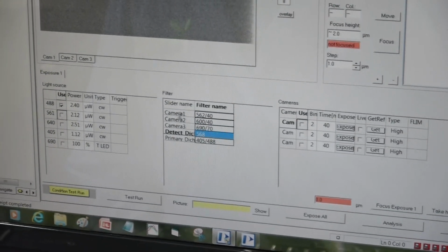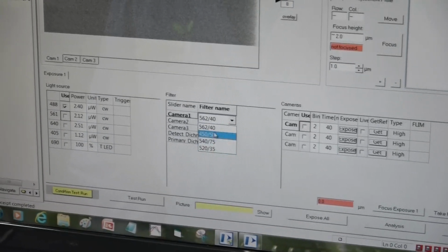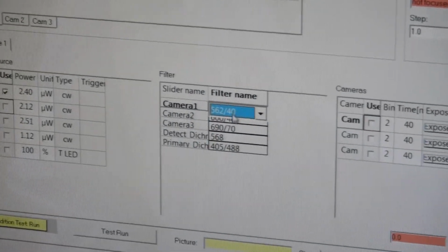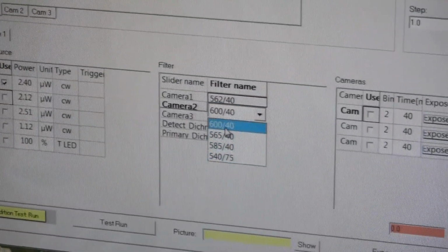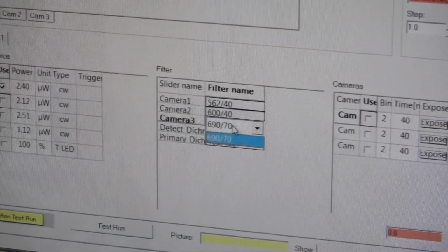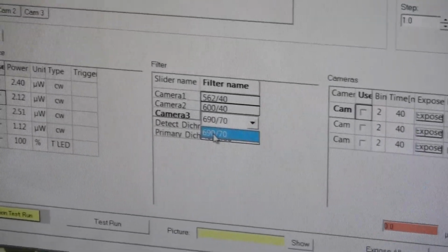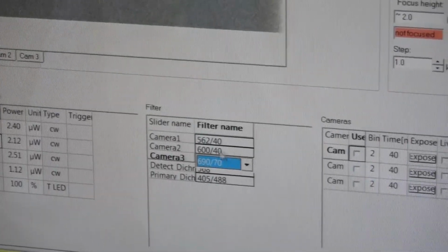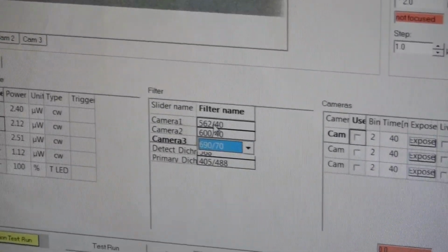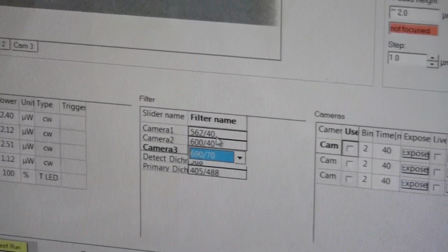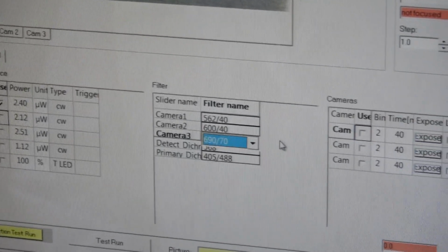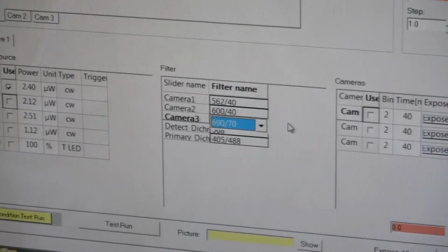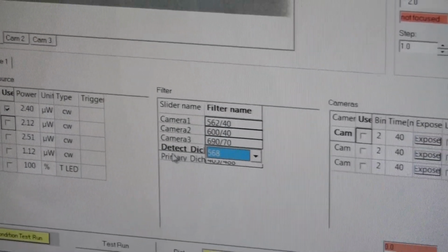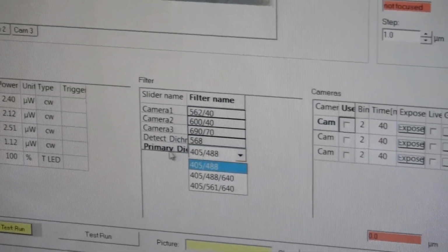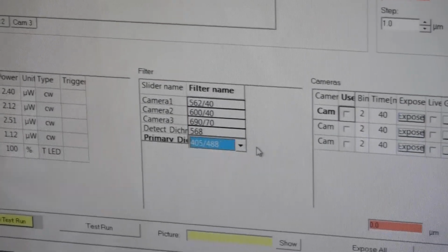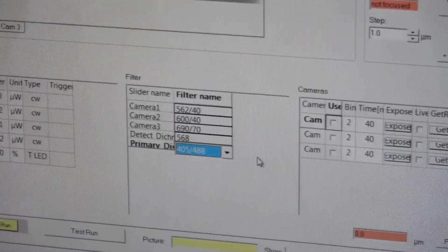So over here you can again see the cameras. On each camera you have multiple filter options that drop down you can pick from. Camera 1 there, you got camera 2, again multiple filters, these are all installed. So you have just a myriad of combinations. Now the camera 3 has only got one filter, there's no changing for it. So it makes it nice, so you can set the filters for each camera, you can capture a different image of the fluorescent, you can overlay the cameras and just get a beautiful picture of the image overlaid with just colors of each camera. And then down here you got some of the dichroic filters. This is your primary. So right now we're just going to use the 405, 488. That'll give us good images on actually all three cameras.